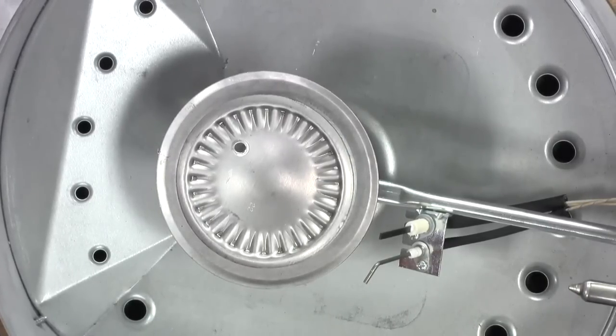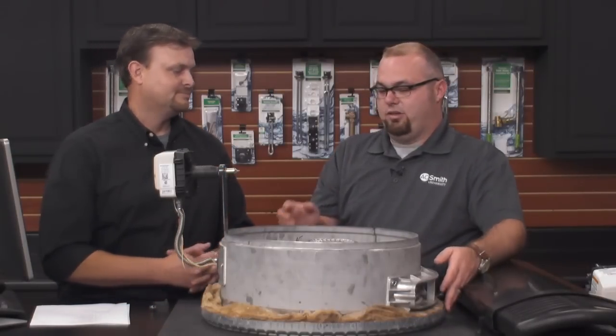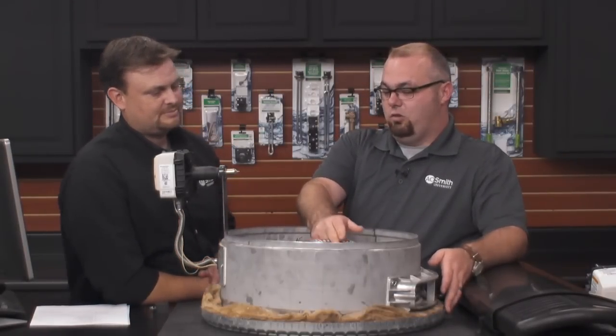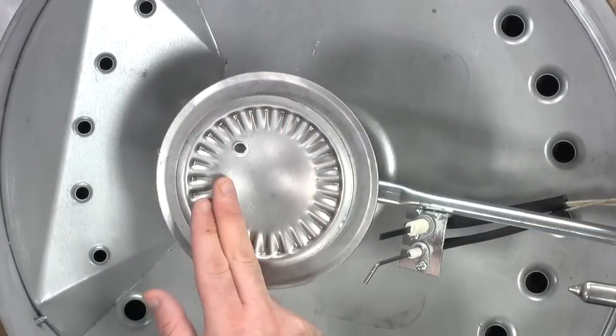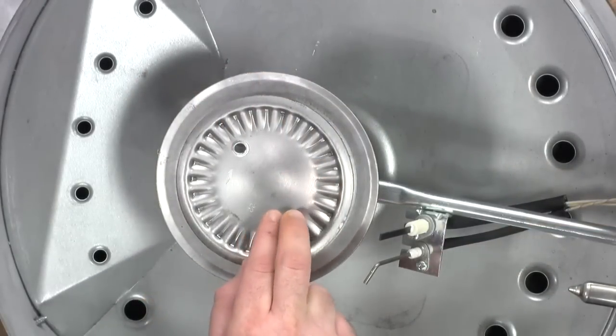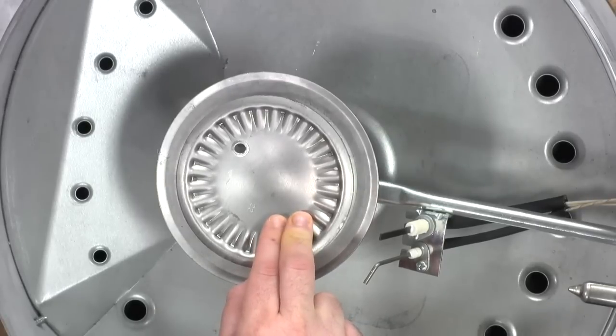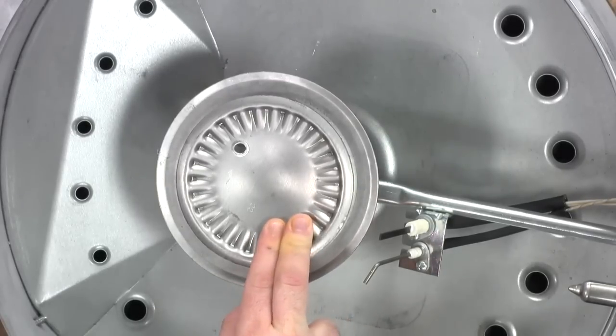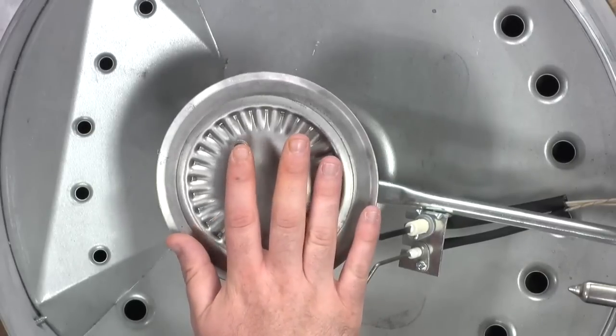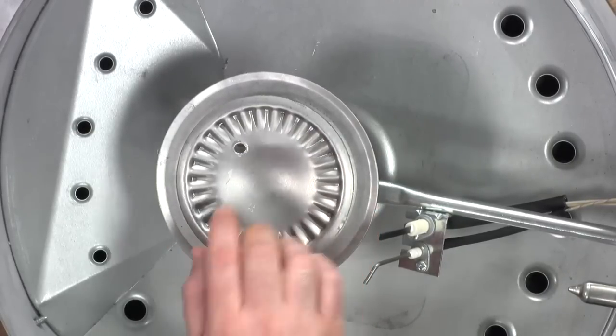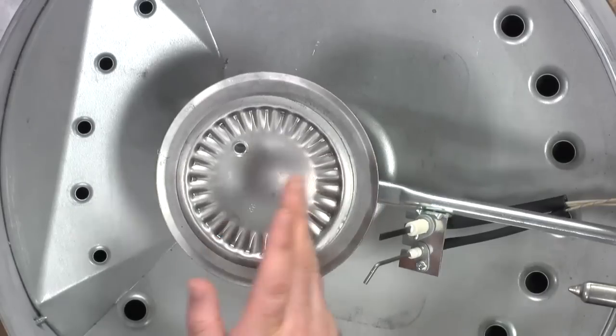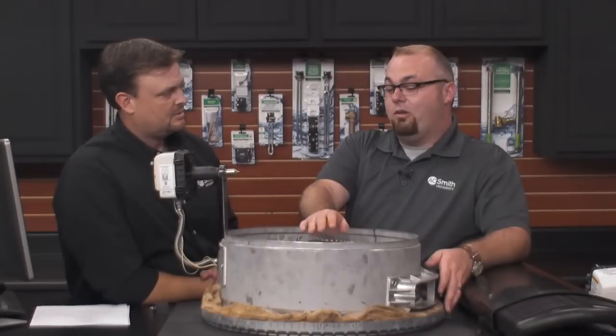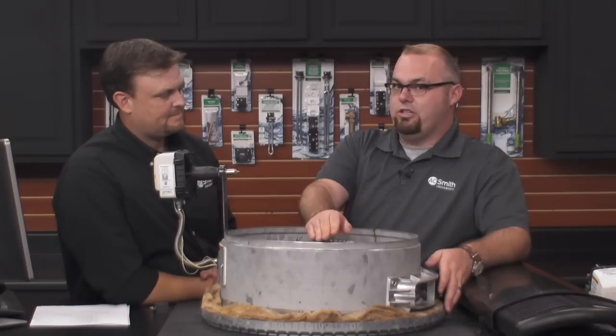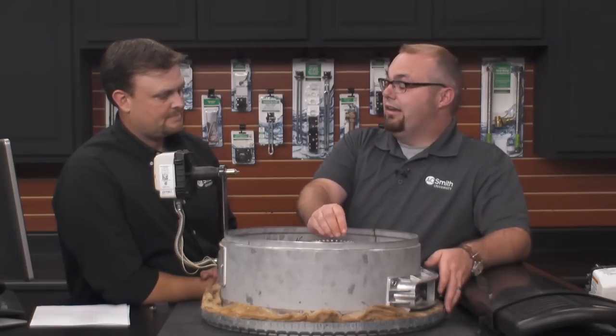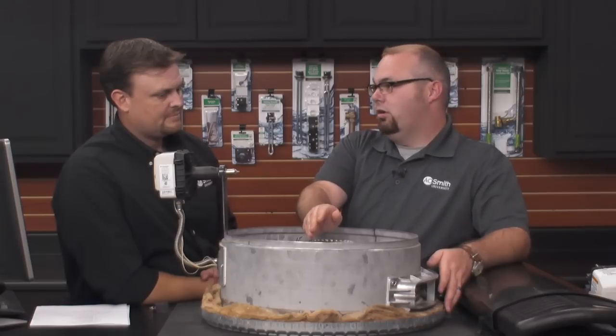And with a Category 3 appliance like this, some condensation is expected, right? Especially when the heater fires off. On a typical burner, you have this little dip right here to catch condensation, just this little bowl. But with this heater, since a little bit more condensation can happen, we have a little drain hole right here where it will drain down and just burn off on the radiation shield. Okay, so that's one good thing. Like I said, it's not really a condensing heater, but it is more energy efficient, so you might get a little bit more condensation compared to the older power vent water heaters.